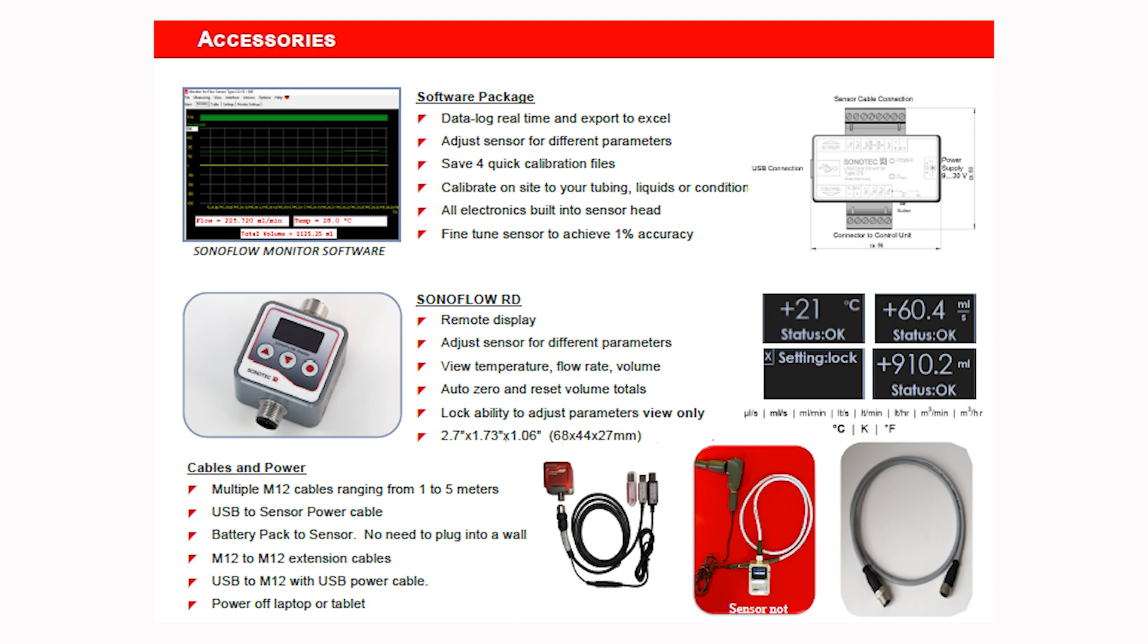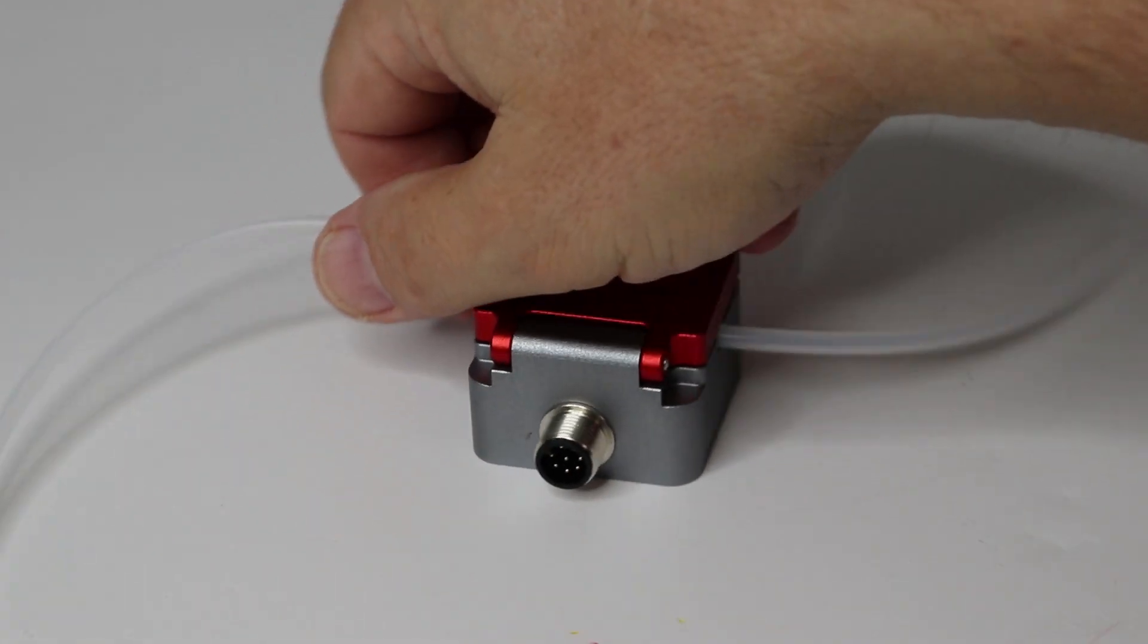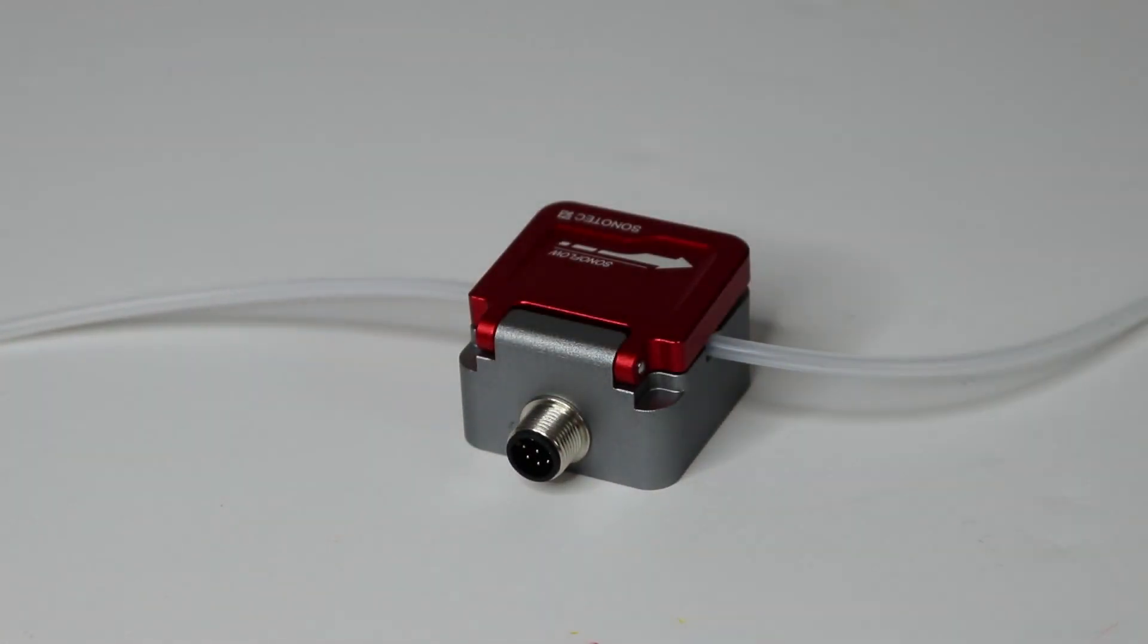As far as the input signals, let's turn this guy around here. We have this port right here. And basically, the operating voltage is 12 to 30 volt VDC. The maximum consumption is 30 milliamps. This electrical connection here is an 8 pin M12 connector.